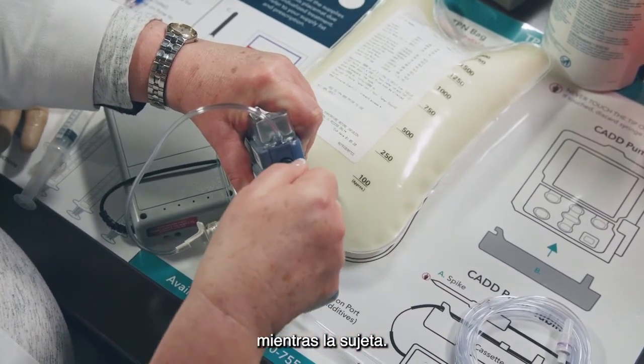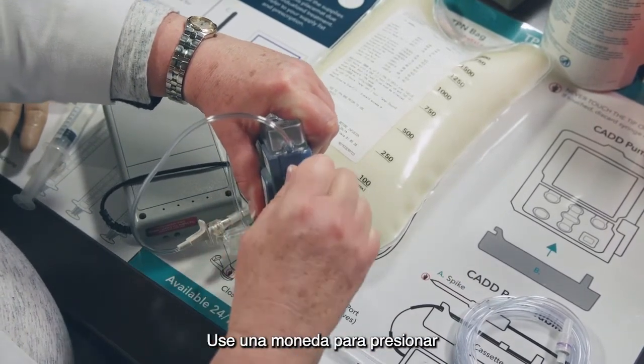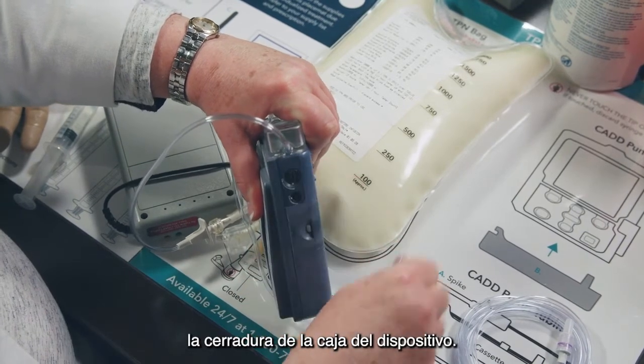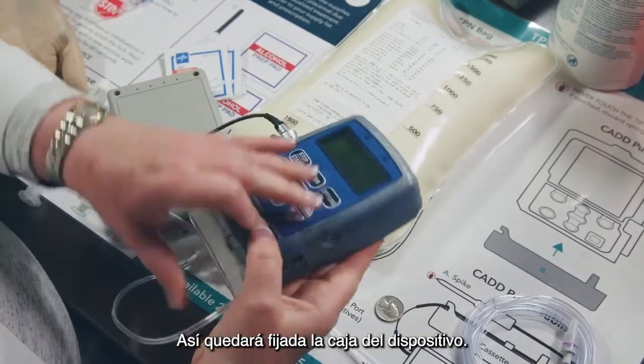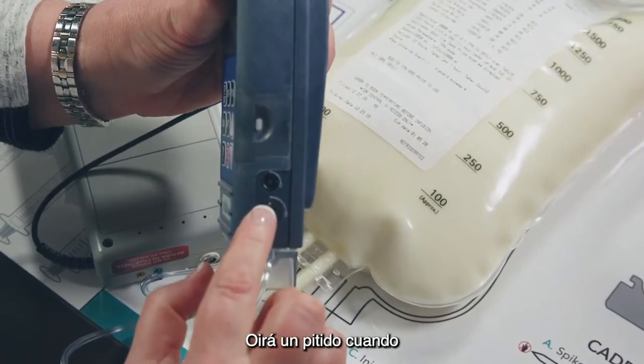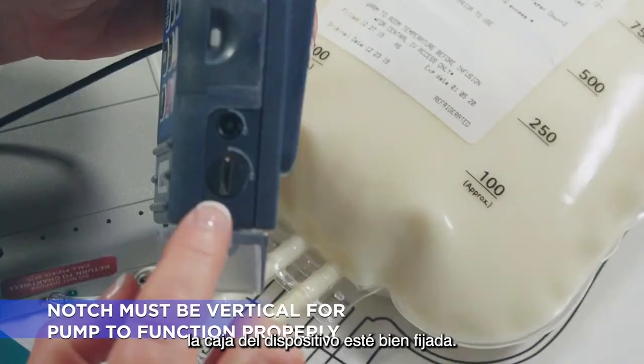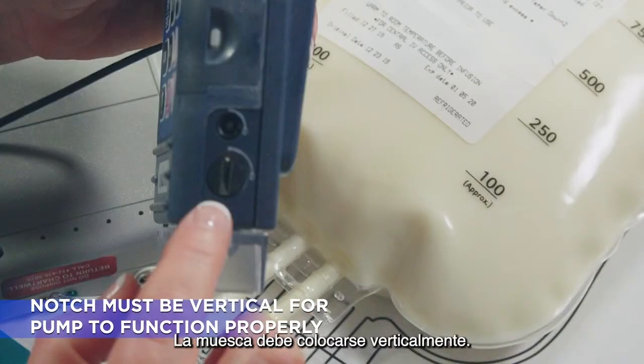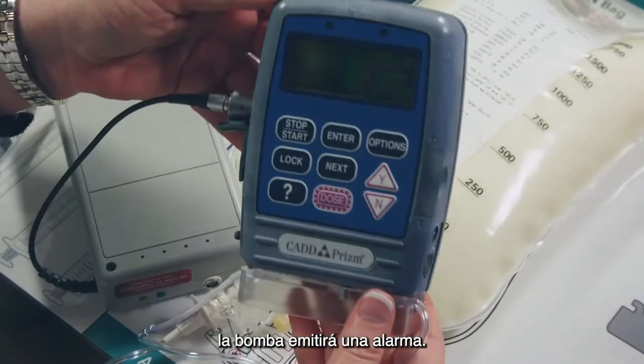While holding the cassette in place, use a coin to push in and turn the cassette lock counterclockwise. This locks the cassette in place. You'll hear a beep when the cassette is securely locked. The notch must be vertically positioned. If it's not fully engaged, the pump will alarm.